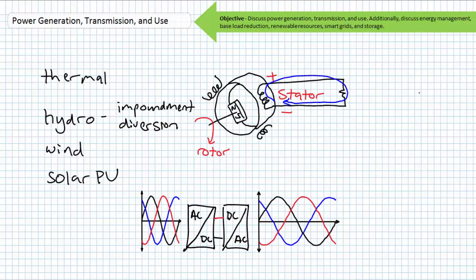Consider the process of full conversion, where a generator produces wild three-phase AC in response to varying wind speeds. Wild means AC without regard to magnitude, frequency, phase shift, or sequence. This is completely converted into DC via rectification, and again inverted into tame three-phase AC with the correct magnitude, frequency, phase shift, and sequence for export to the grid.